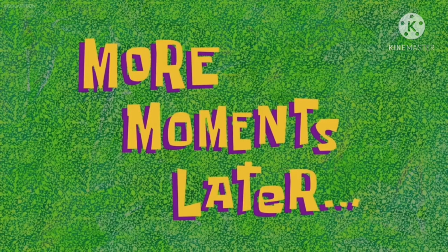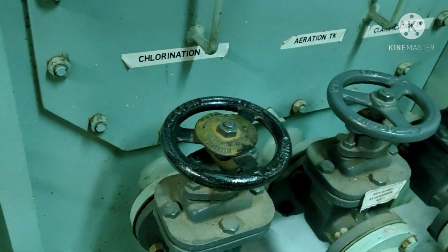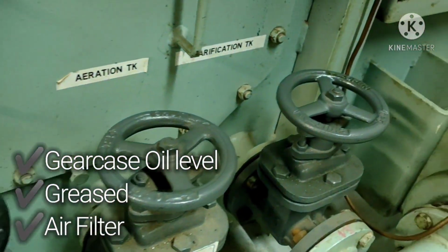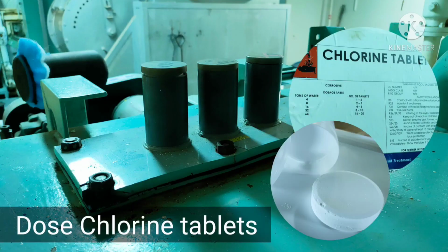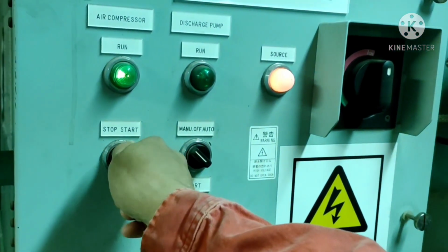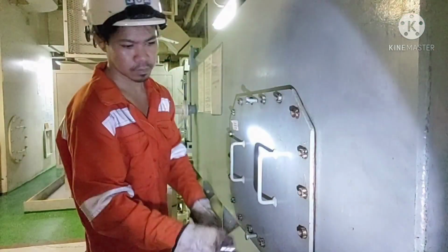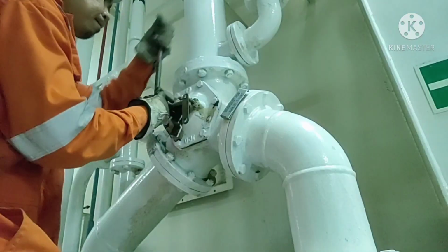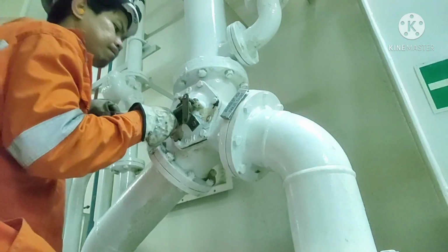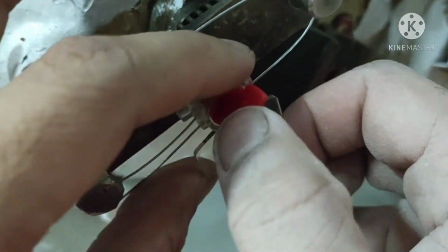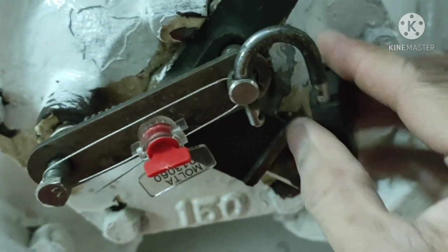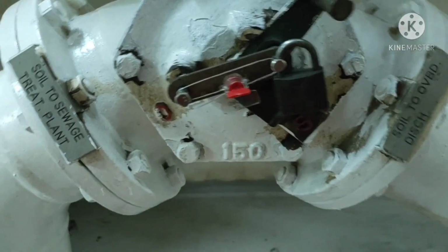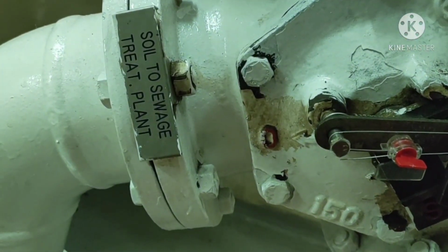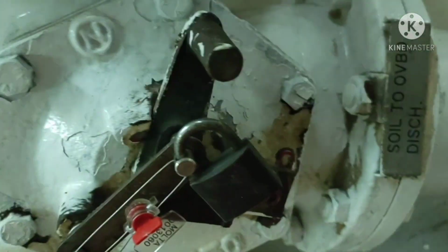Put back all valves in normal position, and check the air blower oil, grease, and air filter. Dose chlorine tablets in the chlorinator, then change the air blower and discharge pump from manual to auto. Then change over the three valves from overboard to the plant. Install a company seal and padlock. Now, our sewage treatment plant is back in service.